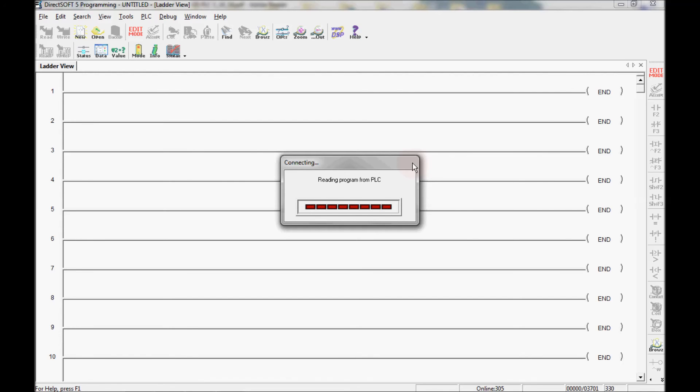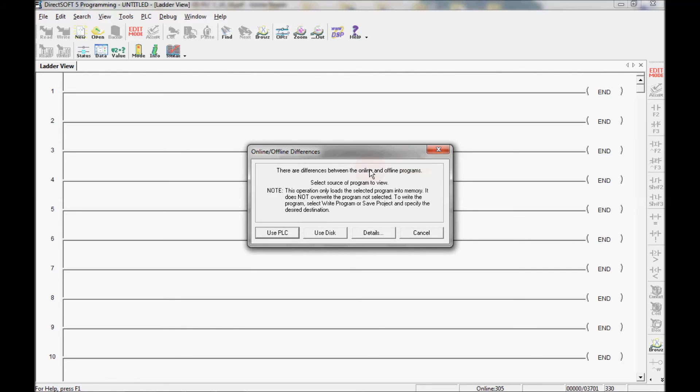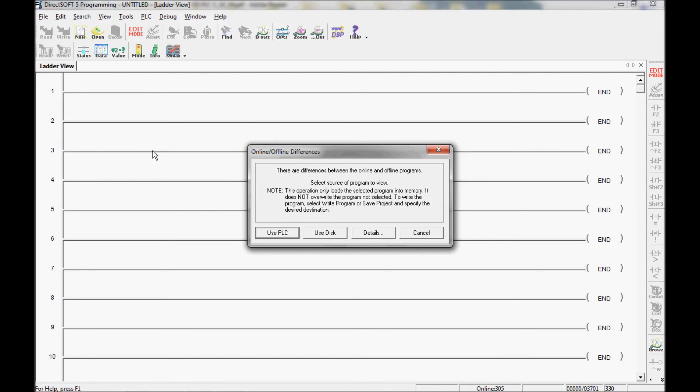It's reading the program within the PLC. It should come up with a window stating that there are differences between the online and offline version. I can either use the PLC or I can use the disk. If I use the disk whatever is up here now will be displayed. That will not be what's in the PLC but that's what I will be displaying. If I want to download it to the PLC I'll have to write the project. Or I can use the PLC and if I use that my documentation may not be right. Or I can come here to details and view the differences.